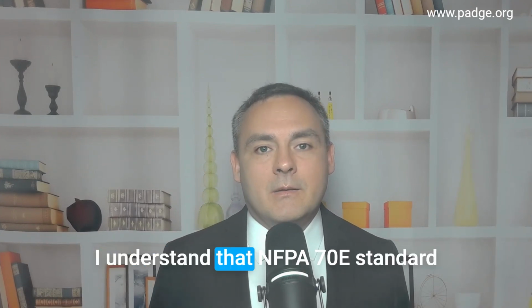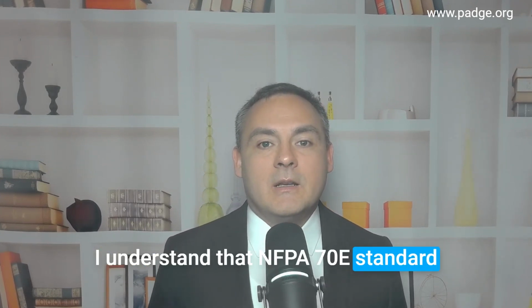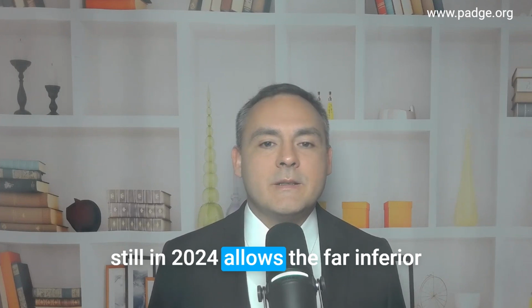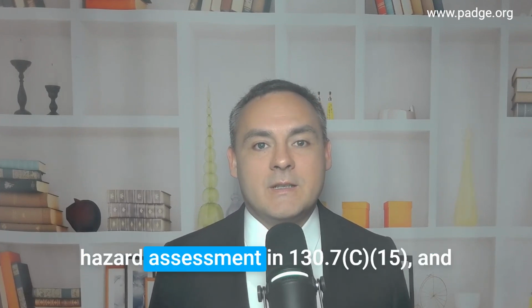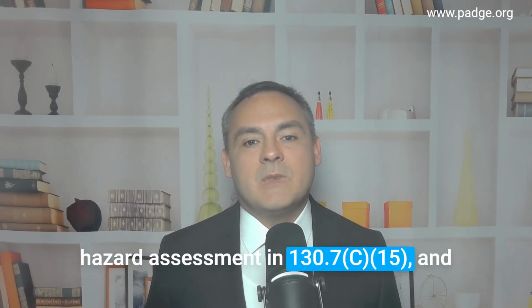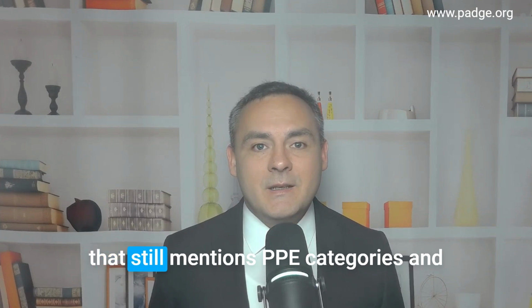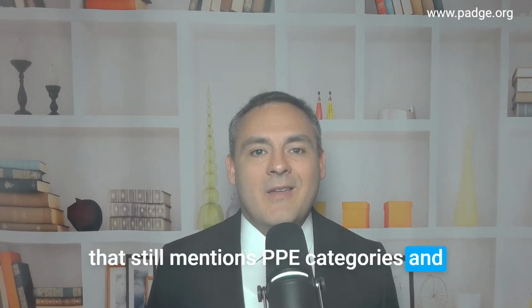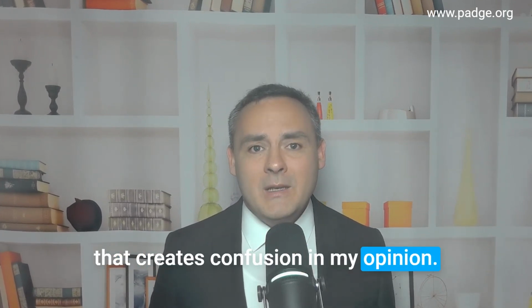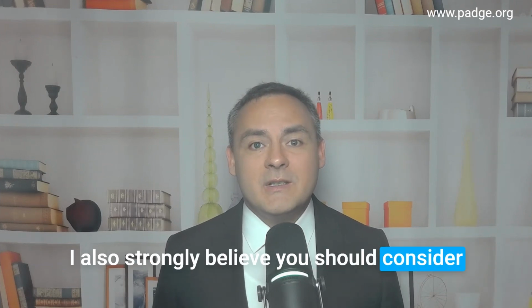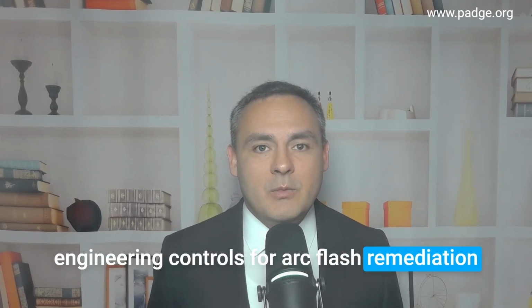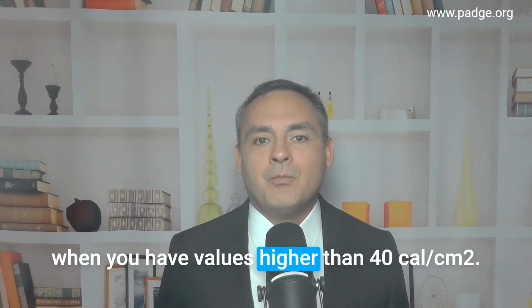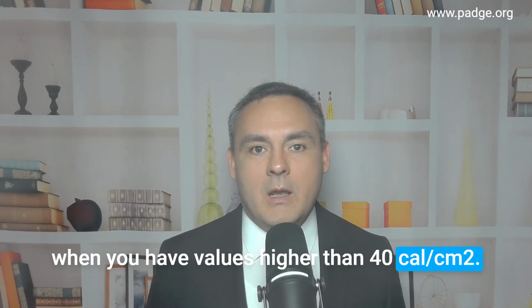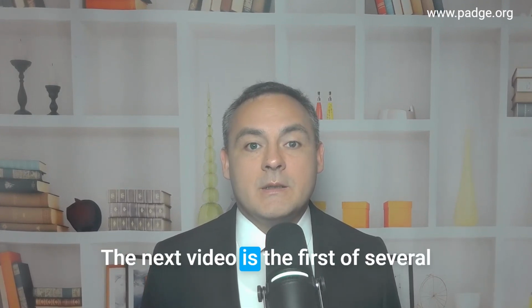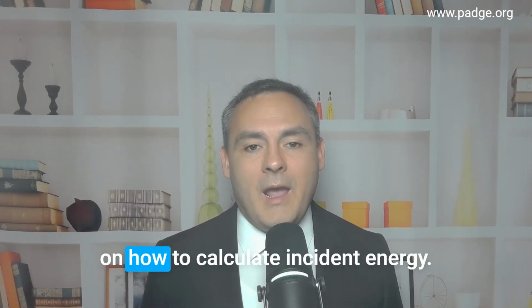I understand that NFPA 70E, still in 2024, allows the far inferior hazard assessment in 130.7(C)(15), and that still mentions PPE categories, and that creates confusion in my opinion. I also strongly believe you should consider engineering controls for arc flash remediation when you have values higher than 40 calories per centimeter squared. The next video is the first of several on how to calculate incident energy. It's going to be fun.